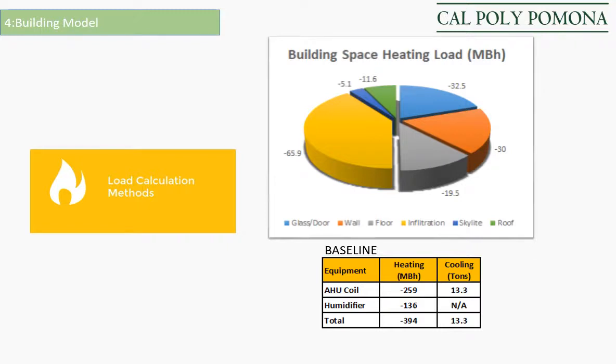The transfer function method was used for the heat load calculation because it was more in-depth than other methods. The radiant time series was used to find the cooling load because it was considered the best fit method for this application. The cooling design day temperature is 53 degrees Fahrenheit dry bulb, 51 degrees wet bulb. Heating design day temperature, 24 degrees Fahrenheit dry bulb. The heating design day heat loss is 164.7 MBh.